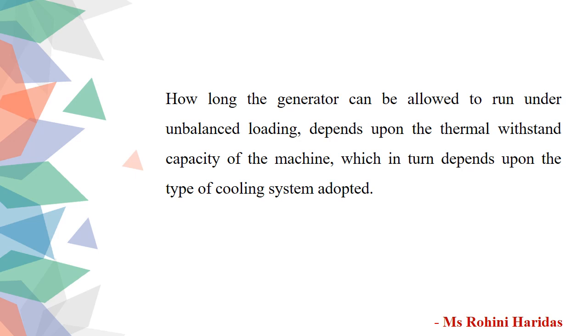How long the generator can be allowed to run under unbalanced loading depends upon the thermal withstand capacity of the machine, which in turn depends upon the type of cooling system adopted.